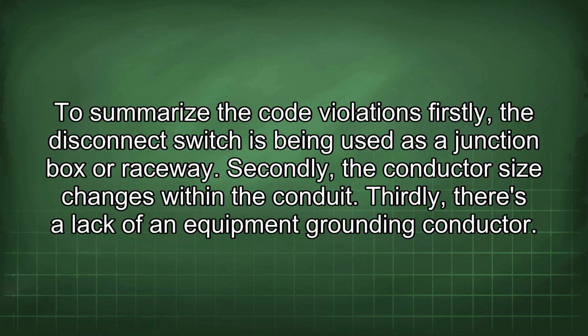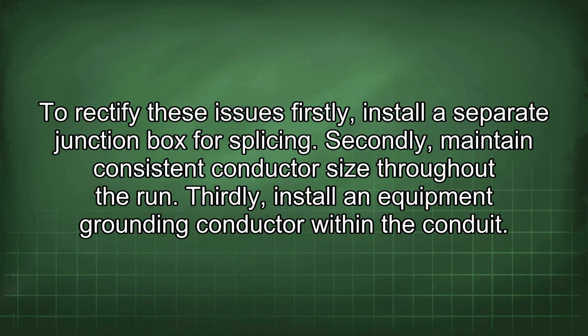To summarize the code violations, firstly, the disconnect switch is being used as a junction box or raceway. Secondly, the conductor size changes within the conduit. Thirdly, there's a lack of an equipment grounding conductor. To rectify these issues, firstly, install a separate junction box for splicing. Secondly, maintain consistent conductor size throughout the run. Thirdly, install an equipment grounding conductor within the conduit.